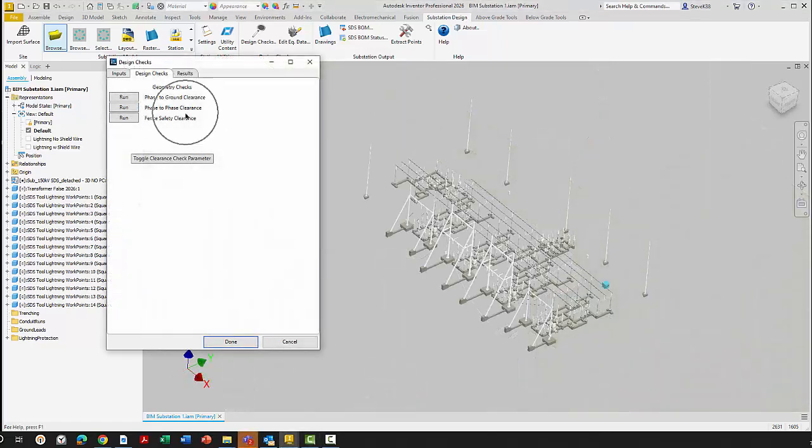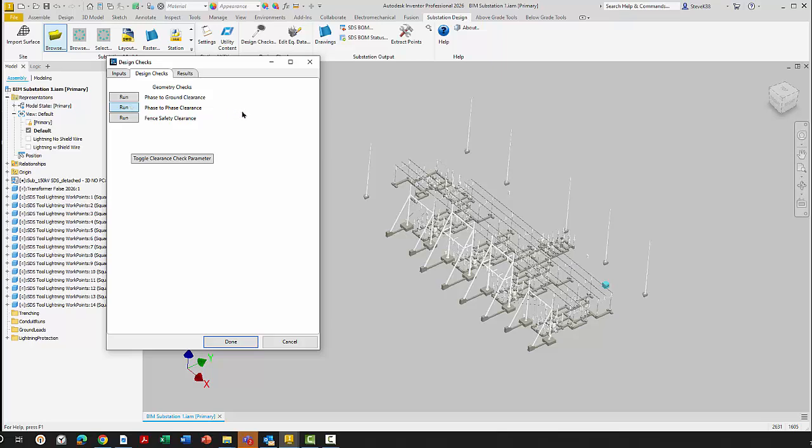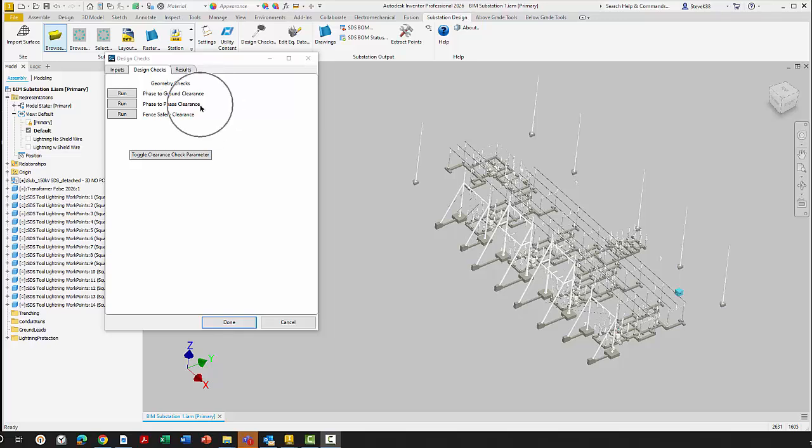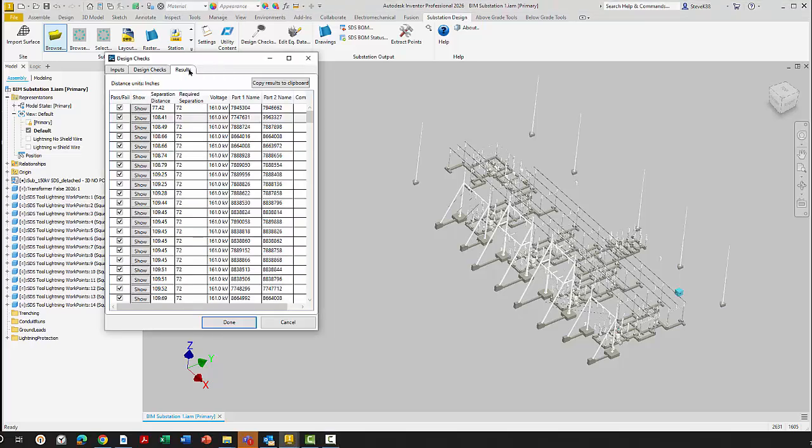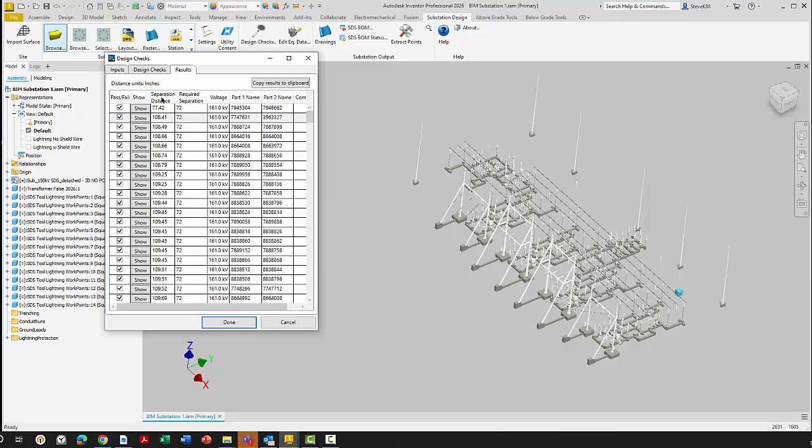We'll run phase to phase clearance check. It often runs a little faster than the phase to ground or live to ground check. So we'll let this run. The phase to phase clearance is complete. We're going to come over to results and you can sort on the separation distance just like what we've done before. This one is fairly close, so we want to look at this one. If I highlight it, we don't really see it that well. I can barely see it on mine. I'm just going to point out a couple of things to help highlight.